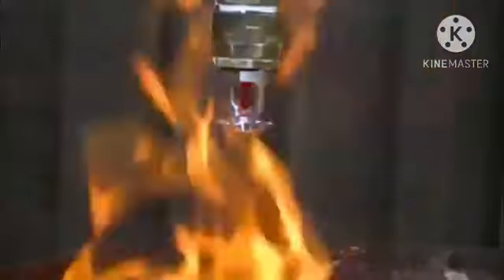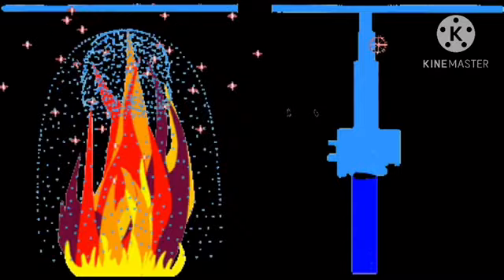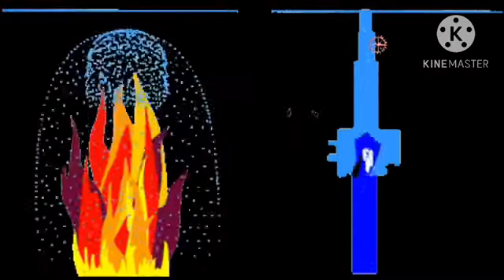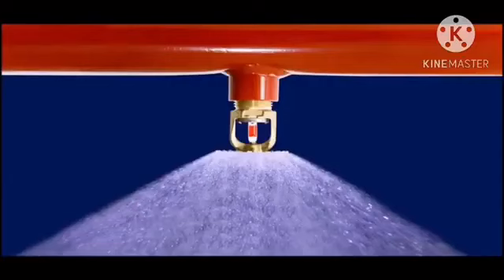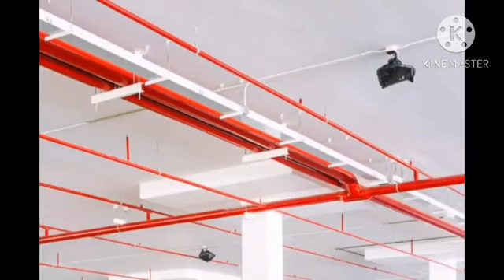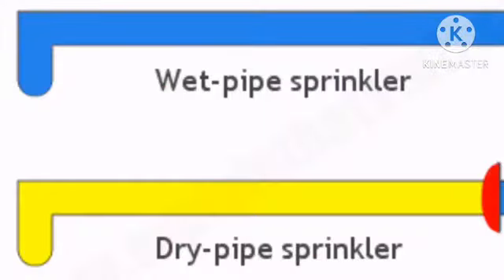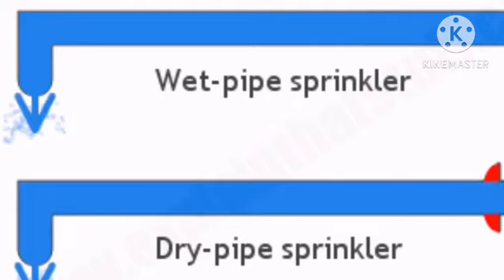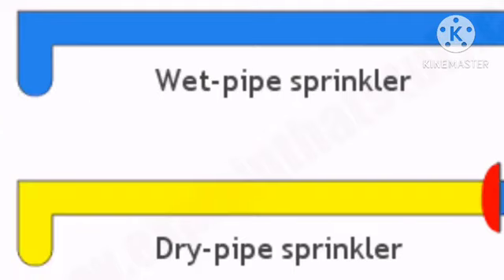These systems are most effective in the fire's initial growth stage, as they work to spread a continuous flow of water over the fire, ideally dampening it enough to be fully put out. There are several types of fire sprinklers. Wet pipe sprinkler systems are filled with water at all times, allowing for quick fire suppression. They are the most common type of sprinkler and are both cost-efficient and low maintenance.